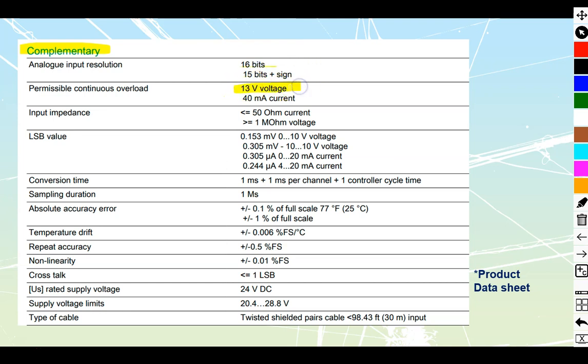We can bring up to 13 volts into this thing or up to 40 milliamps current if we were doing the current one. They give us the least significant bit value. In other words, the smallest amount of voltage change that it's going to be able to register. So if I'm on the 0 to 10 volt, it's going to be able to register 0.153 of a millivolt, or 153 microvolts, as the smallest amount of change.